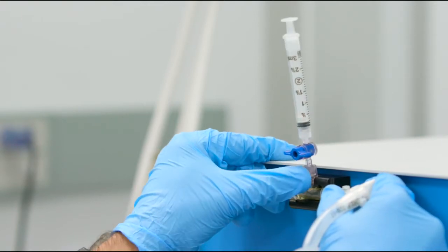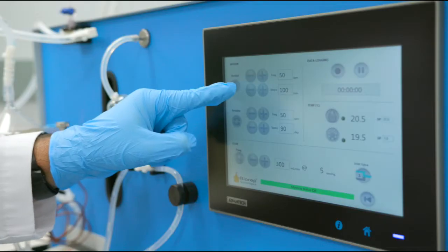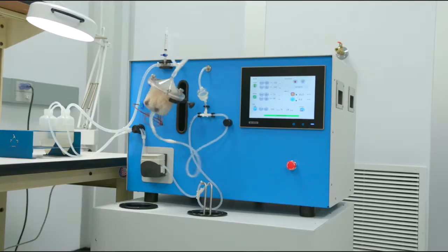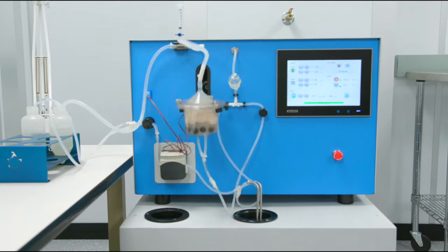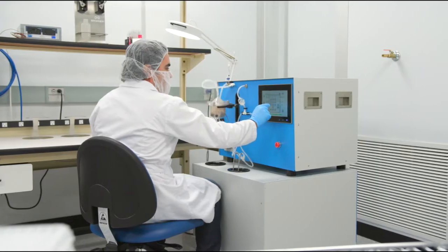Now in its fifth version, the Ricordi isolator software enables users to store a time-lapse record of every parameter used during the procedure, an important feature because it allows a repeatable and efficient isolation process every single time. This saves valuable time and avoids costly yield issues during the isolation.